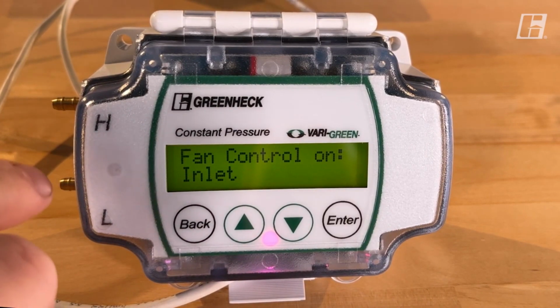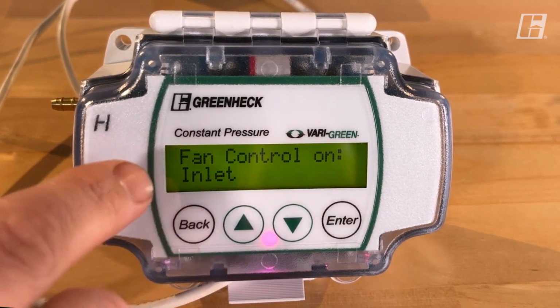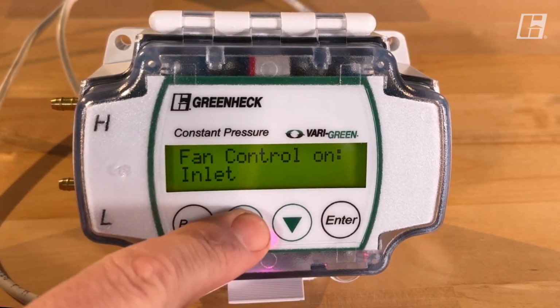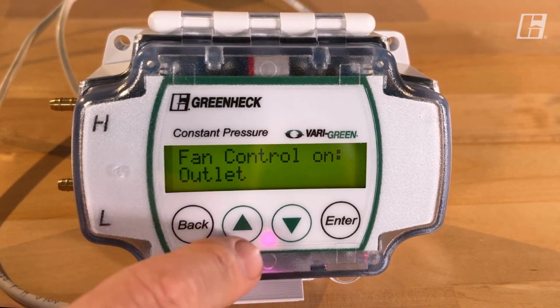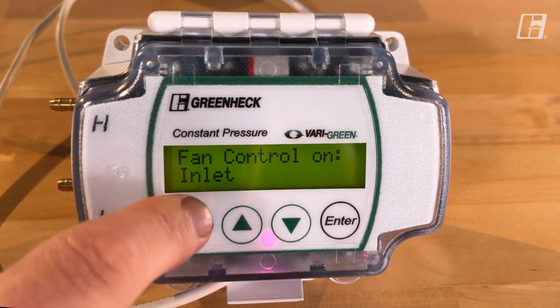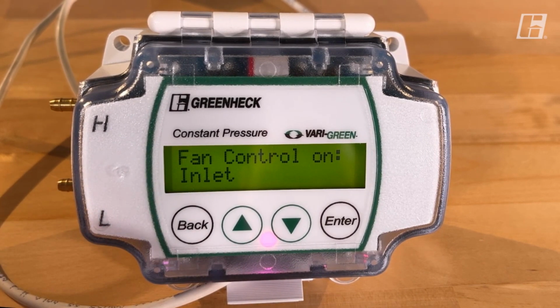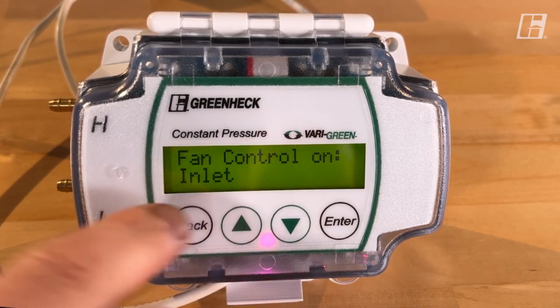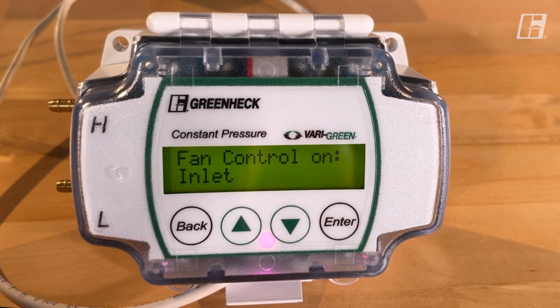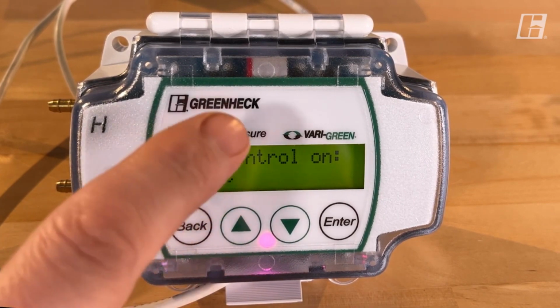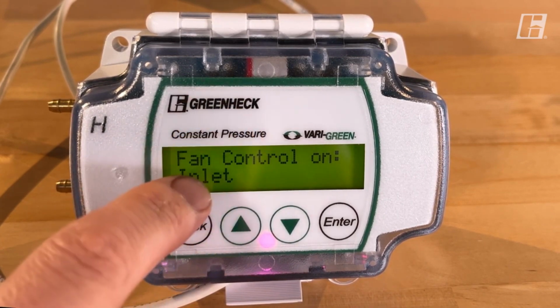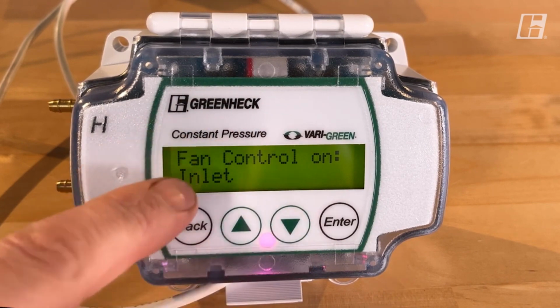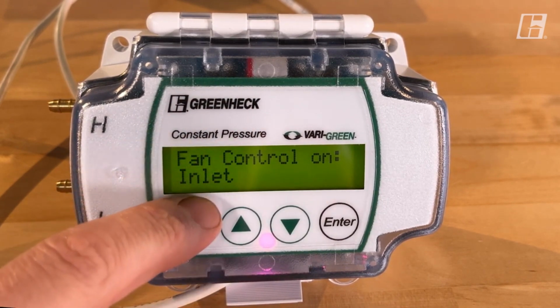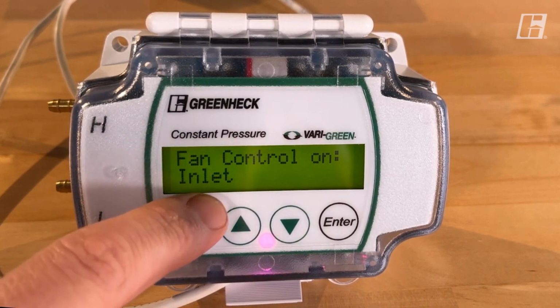Now this is probably the most important one of this entire video. Fan control on inlet or outlet. What it's asking is, where is the probe? Is the probe on the inlet side of the fan or the outlet side of the fan? If this one's incorrect, all your readings are going to be opposite, negative versus positive. So for our scenario, our fan is on the roof, and this is in the ductwork. So we're going to say fan control is on the inlet, and we're controlling the fan on the roof.